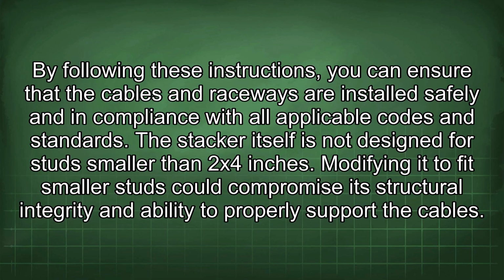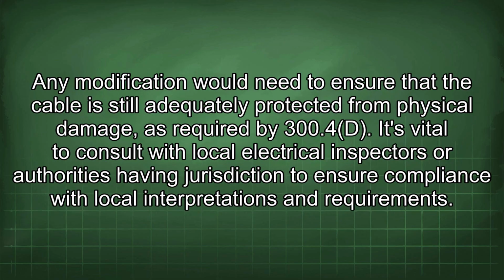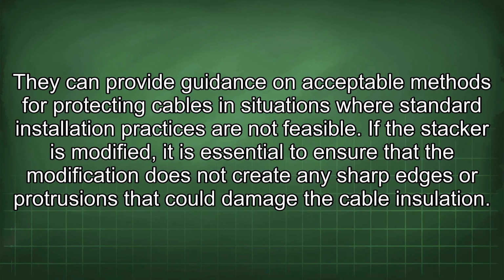applicable codes and standards. The stacker itself is not designed for studs smaller than 2x4 inches. Modifying it to fit smaller studs could compromise its structural integrity and ability to properly support the cables. Any modification would need to ensure that the cable is still adequately protected from physical damage as required by 300.4d. It's vital to consult with local electrical inspectors or authorities having jurisdiction to ensure compliance with local interpretations and requirements. They can provide guidance on acceptable methods for protecting cables in situations where standard installation practices are not feasible.